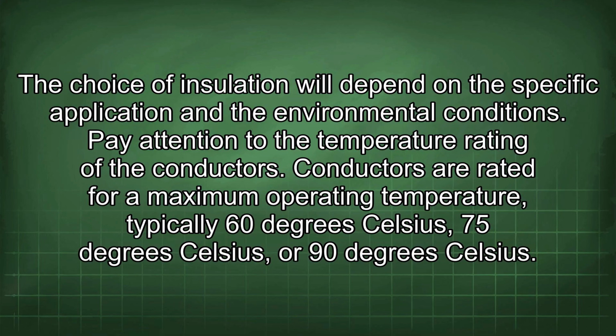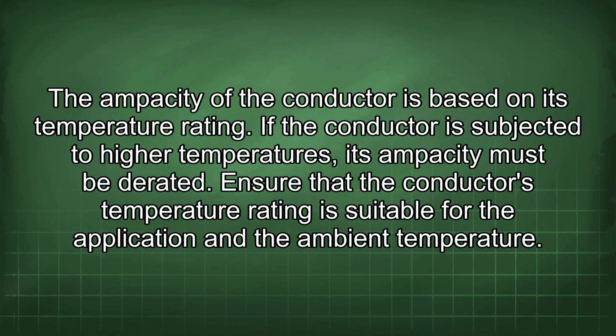Pay attention to the temperature rating of the conductors. Conductors are rated for a maximum operating temperature, typically 60 degrees Celsius, 75 degrees Celsius, or 90 degrees Celsius. The ampacity of the conductor is based on its temperature rating. If the conductor is subjected to higher temperatures, its ampacity must be derated. Ensure that the conductor's temperature rating is suitable for the application and the ambient temperature.